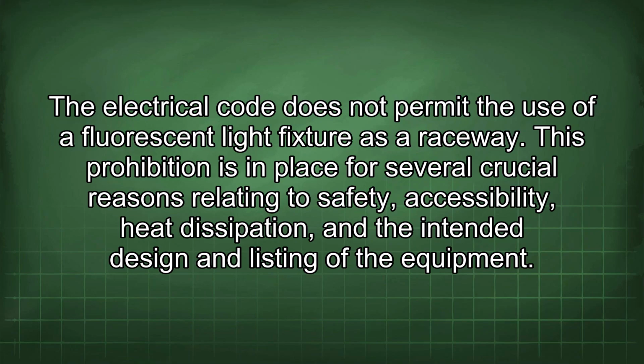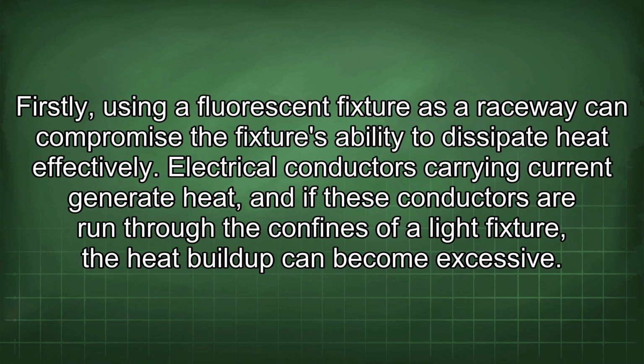Electrical code does not permit the use of a fluorescent light fixture as a raceway. This prohibition is in place for several crucial reasons relating to safety, accessibility, heat dissipation, and the intended design and listing of the equipment. Firstly, using a fluorescent fixture as a raceway can compromise the fixture's ability to dissipate heat effectively. Electrical conductors carrying current generate heat, and if these conductors are run through the confines of a light fixture, the heat buildup can become excessive.